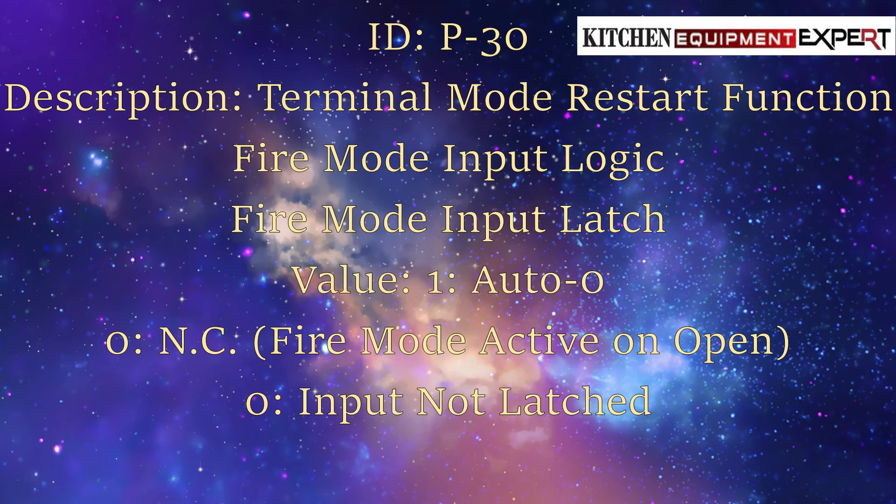ID Parameter P30. Description: Terminal Mode Restart Function, Fire Mode Input Logic, Fire Mode Input Latch. Value: 1 - Auto, 0, 0 - NC Fire Mode Active On Open, 0 - Input Not Latched.